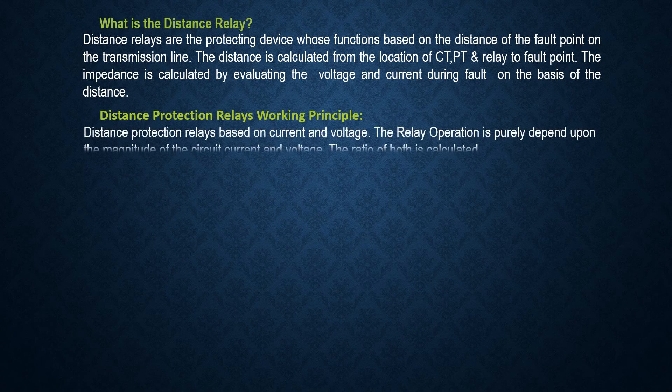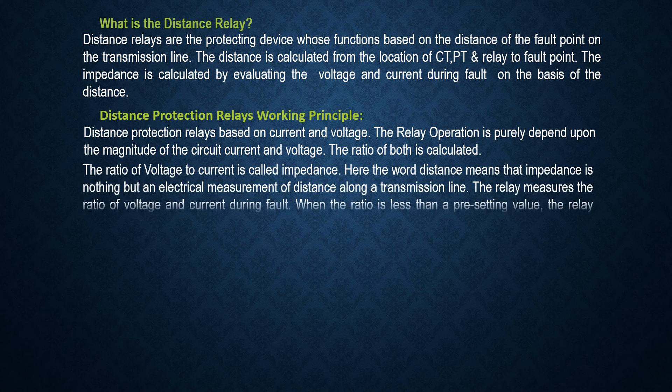Distance protection relays are based on current and voltage. The relay operation purely depends upon the magnitude of the circuit current and voltage — the ratio of both is calculated. The ratio of voltage to current is called impedance. The relay measures the ratio of voltage and current during a fault; when the ratio is less than a preset value, the relay operates to trip the circuit breaker.